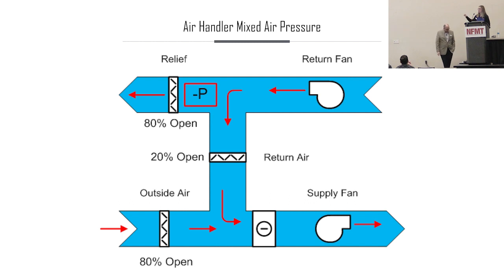Another indication with this system, though, if you want to make sure that you're actually bringing in outside air, if you think you've got any issues with that, along with if you have a return fan system, making sure that that is not a negative number up there, but also if you have a mixed air plenum, if it's a positive pressure, then you're probably not bringing in outside air. I guess in this system. Yep. Before I speak wrong. Okay.